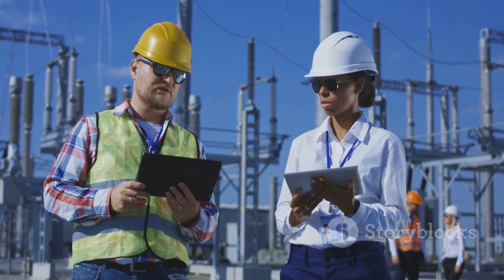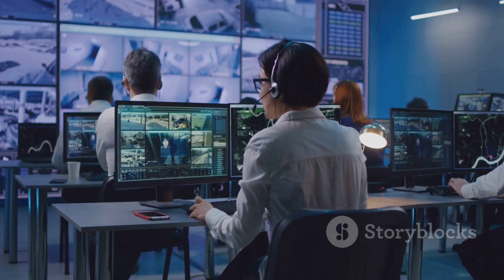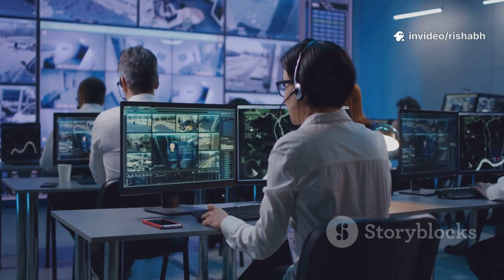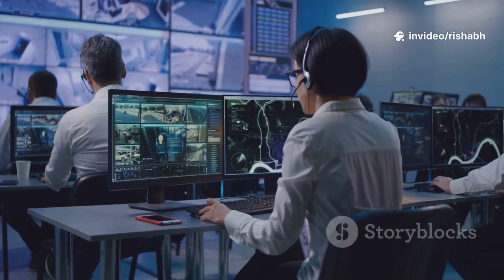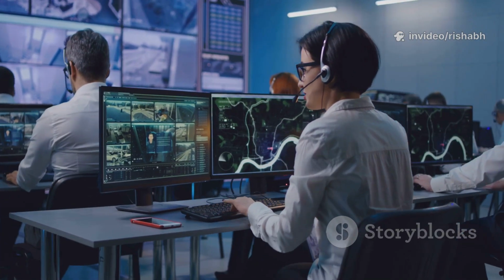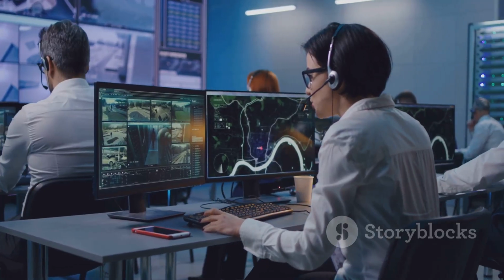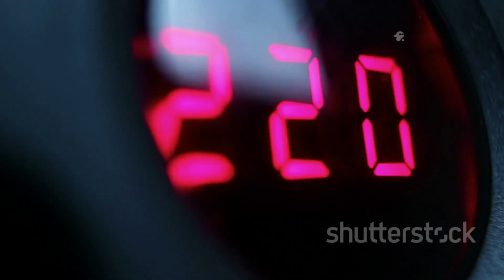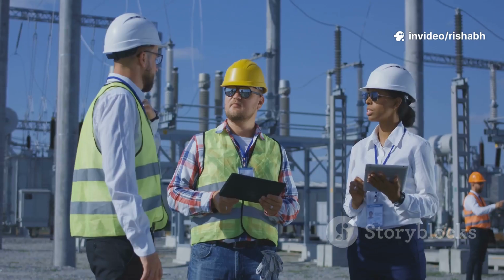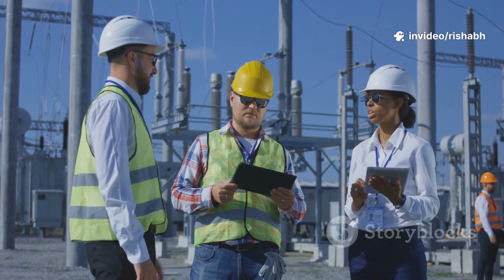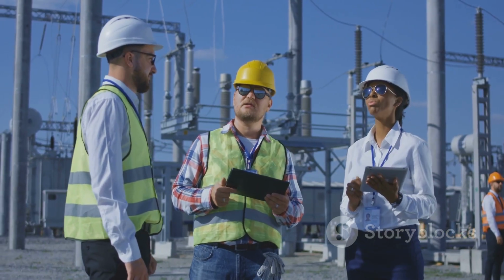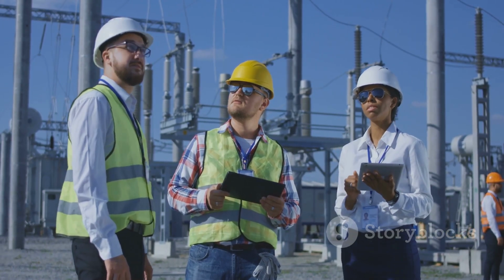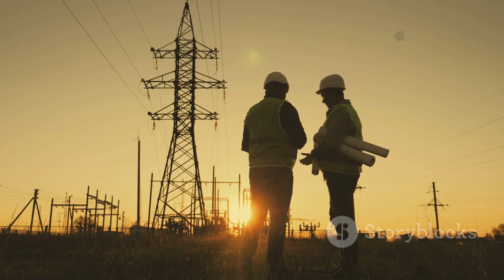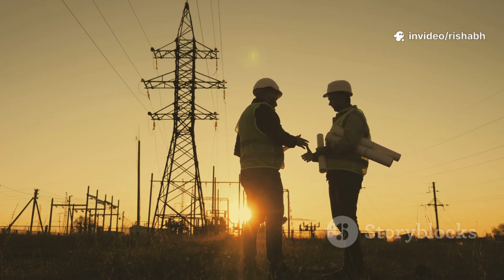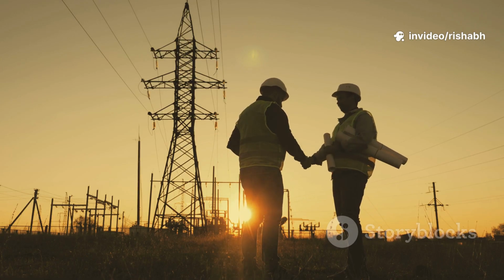Ultimately, all this monitoring translates into smarter maintenance. Instead of servicing transformers on a fixed schedule, whether they need it or not, utilities can use the data from the Multilin 845 to move towards condition-based maintenance. The relay can track the transformer's aging based on how hard it has been working and the temperatures it has experienced. This helps asset managers predict the remaining lifespan of the transformer and decide when it's most cost-effective to repair or replace it. It's all about using science and data to make better decisions, saving money and improving reliability for all of us.